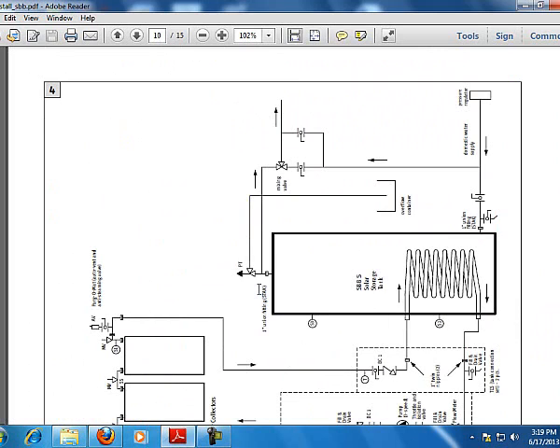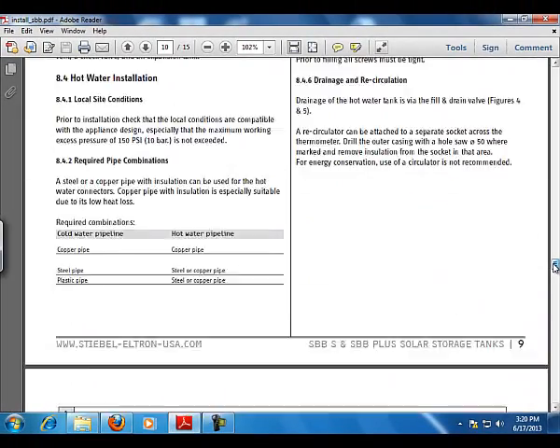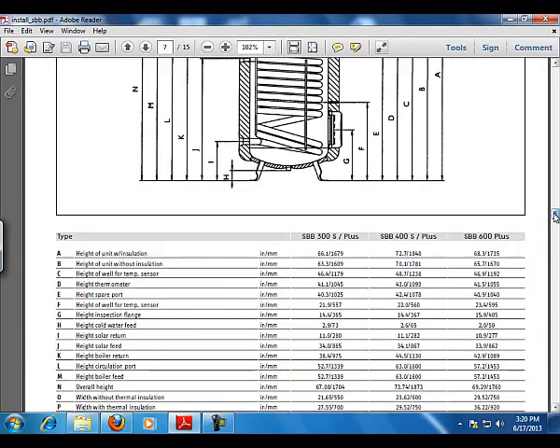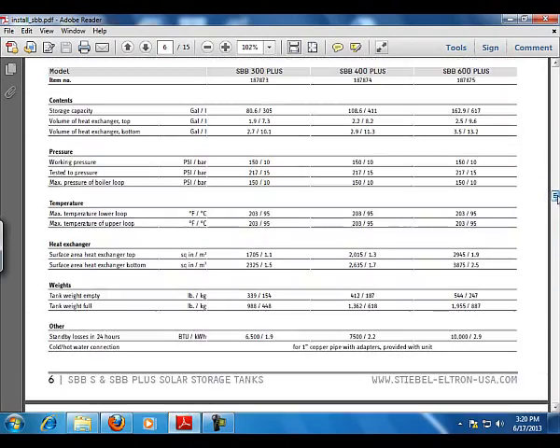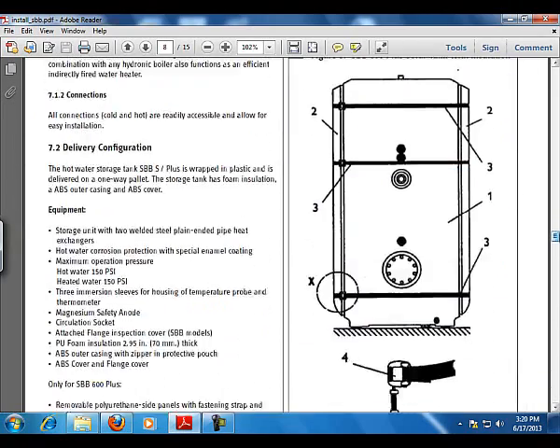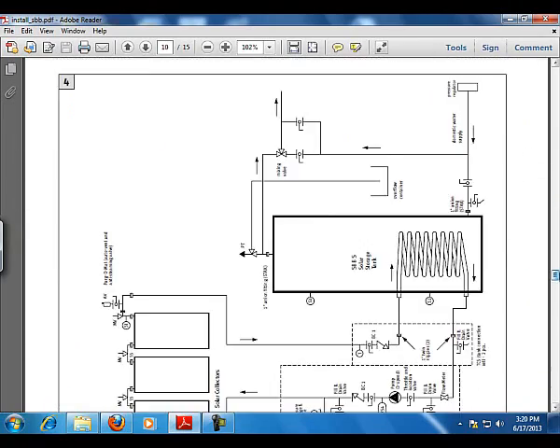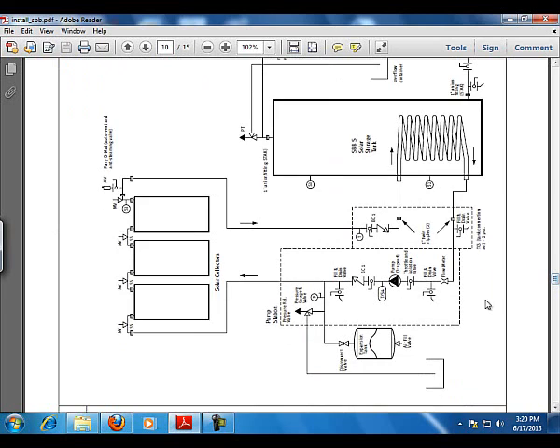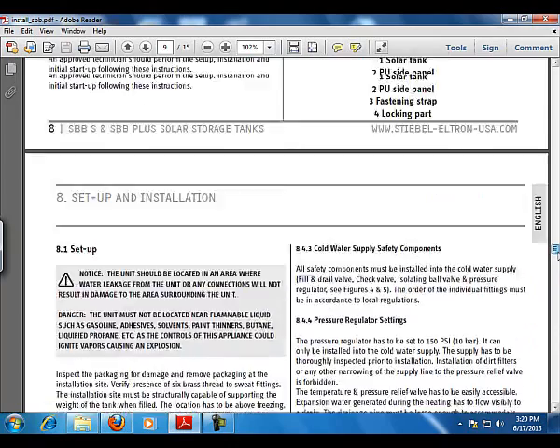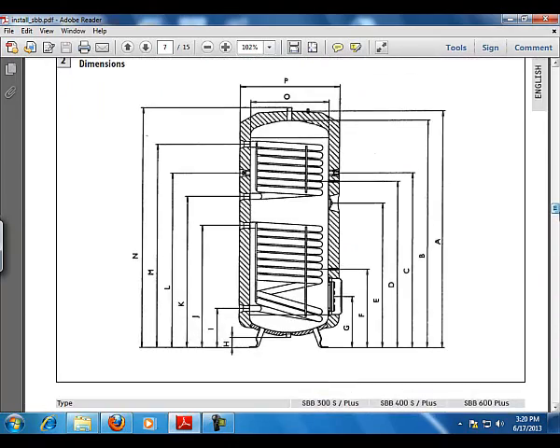We have to have a pressurized tank up here, and then we also want a pressure regulator on here to maintain this pressure inside of the system. What's nice about this is Stiebel Eltron has verified that their system will work upwards of 150 psi, so that's about three times the operating pressure that the municipal water supply will provide you with. Typically, we like to see somewhere near 50 to 60 psi of pressure that's on our water system, and so we can overcome that by three times. That's not the pressure that we're setting our solar collectors and lines and the solar collector pump at, so that system will be at something entirely different. This pressure here typically will be in that 30 psi range, roughly. You could go somewhat higher, and there's some numbers that we'll calculate there, but on the tank and the tank sizing, that's what we have going on.